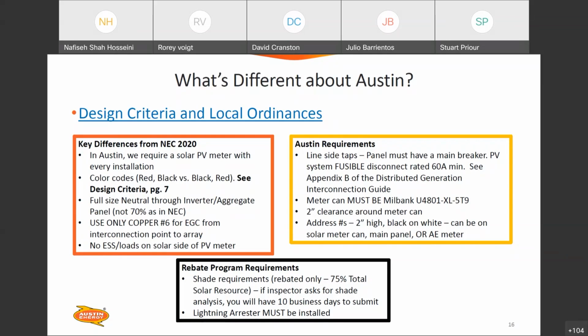You'll also need a full-size neutral through the inverter or the aggregate panel if you've got something like microinverters or optimizers on the roof—everything on the ground, on the wall, needs a neutral the same size as your ungrounded conductors. Another thing above and beyond the NEC is that we require a number 6 copper equipment grounding conductor from the point of interconnection to the array. That number 6 is obviously bigger than what the NEC requires, so pay close attention to that.